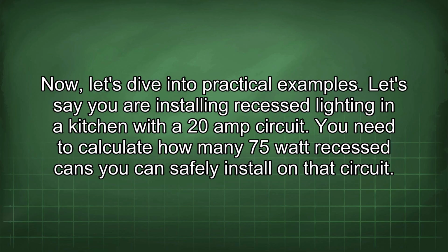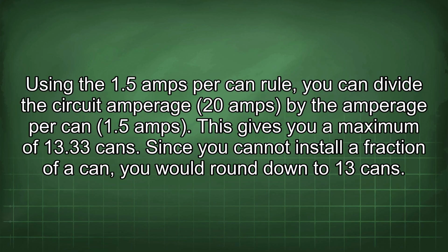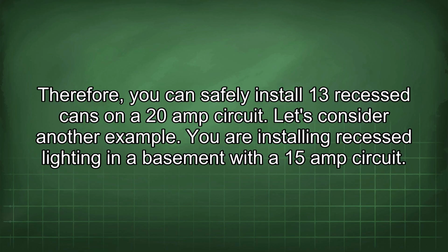Let's say you are installing recessed lighting in a kitchen with a 20 amp circuit. You need to calculate how many 75-watt recessed cans you can safely install on that circuit. Using the 1.5 amps per can rule, you can divide the circuit amperage, 20 amps, by the amperage per can, 1.5 amps. This gives you a maximum of 13.33 cans. Since you cannot install a fraction of a can, you would round down to 13 cans. Therefore, you can safely install 13 recessed cans on a 20 amp circuit.